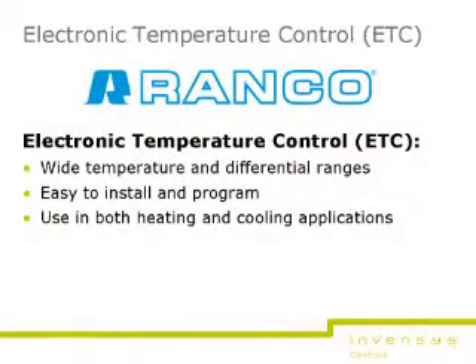Now you are done! To recap, the top 3 reasons to buy a Ranco Electronic Temperature Control are 1. Application flexibility. 2. Upgrade to newer technology from mechanical to electronic controls. And 3. Expanded features such as a wide temperature range, wide differential adjustment, multiple stages, and multi-voltage inputs. The Ranco ETC has wide temperature and differential ranges. It is easy to install and program with the ability to use in both heating and cooling applications. Just a few more reasons why Ranco has been a trusted source in the commercial refrigeration industry for over 50 years. The Ranco Electronic Temperature Control is just another example of innovation that you can expect from Invensys Controls, a product with uncompromising quality and technology innovation.